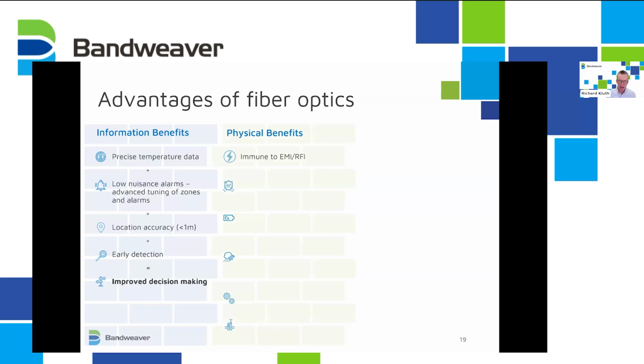Fiber optic sensors are passive, they have no moving parts. It's based on a glass optical fiber, which is immune to electromagnetic and radio frequency interference. So where there are high power sources, it's not at all affected by that. It's made of glass, so it's not susceptible to corrosion. There's no power or electronics in the field, so it's very simple to install and very low maintenance, just a simple cable install.